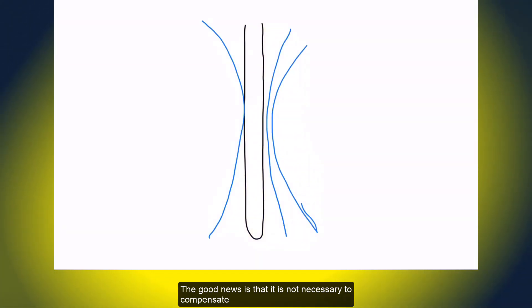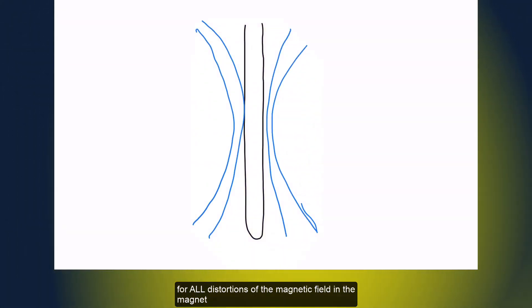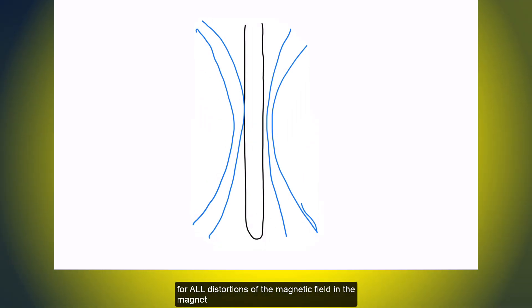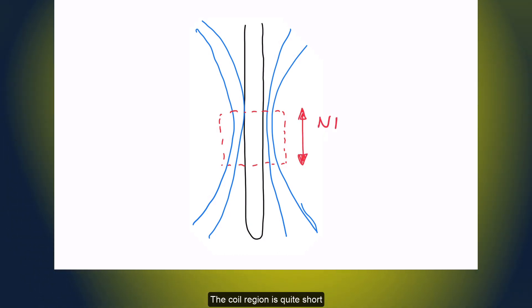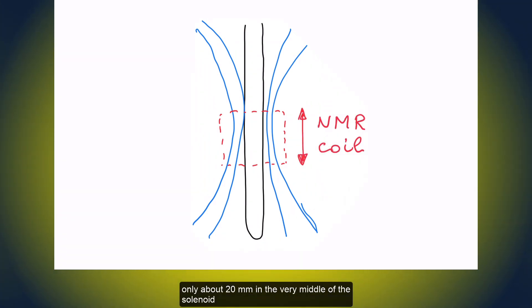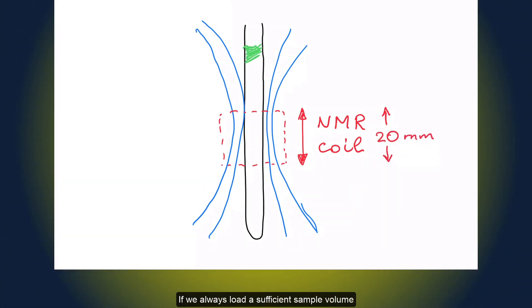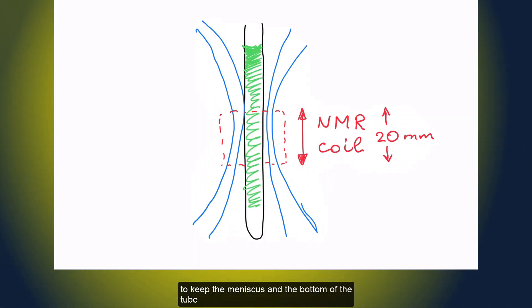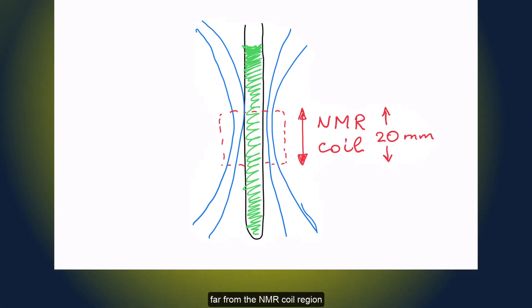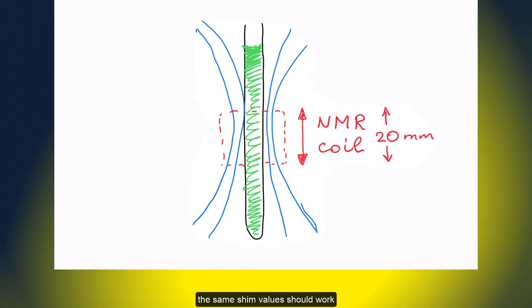The good news is that it is not necessary to compensate for all distortions of the magnetic field in the magnet. We only need to make the field straight where the NMR detection occurs. The coil region is quite short, only about 20 mm in the very middle of the solenoid. If we always load sufficient sample volume to keep the meniscus and the bottom of the tube far from the NMR coil region, the same shim values should work.